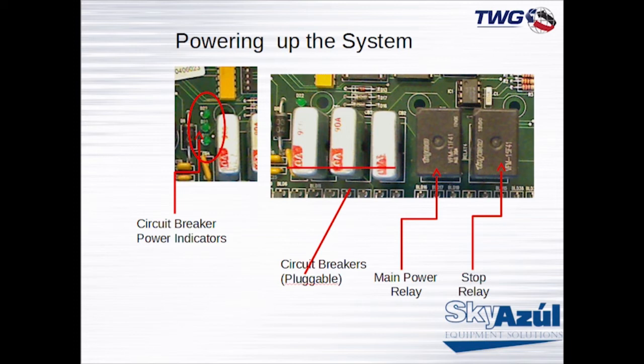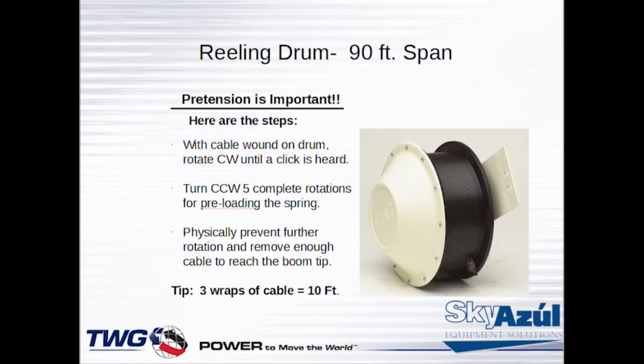So moving on to that, we'll move right on to the reeling drum portion of that system. And on this, I'd like to remind everybody that pretension is important. And here's the steps: with the cable wound on the drum and dead-ended or whatever there, you turn counterclockwise 5 complete rotations for preloading the spring. And then physically prevent rotation and remove enough cable to reach the boom tip.